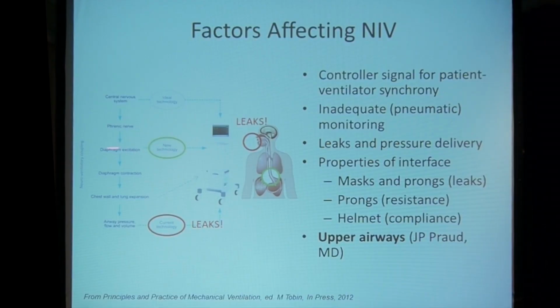So we have our pneumatic controllers. There's also been some work done on the Graseby capsule in the neonatal world. It's a small capsule you place on the abdomen, and it detects movement of the diaphragm. This has been used as a trigger mechanism, but the inspiratory time still has to be dialed in, and still no one has really validated what the Graseby capsule performance is with respect to diaphragm activity. So this is what we've been talking about all day, using the electrical activity of the diaphragm to control the ventilator. And you can see here that this is what we call a pneumatically independent signal. The fact that air is leaking affects these signals, but this is an electrical signal. It's pneumatically independent, and that makes it very ideal for controlling the ventilator.